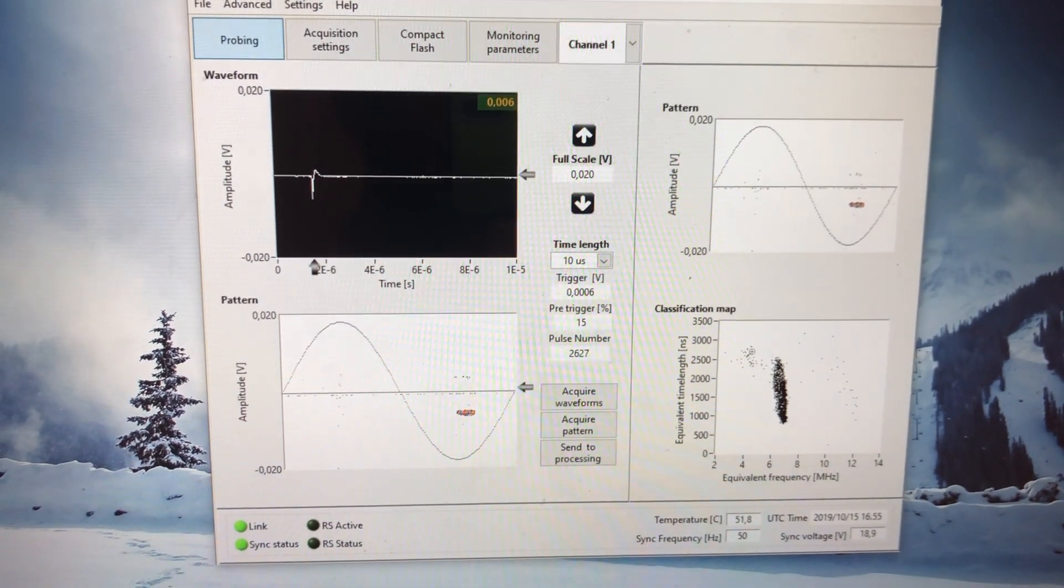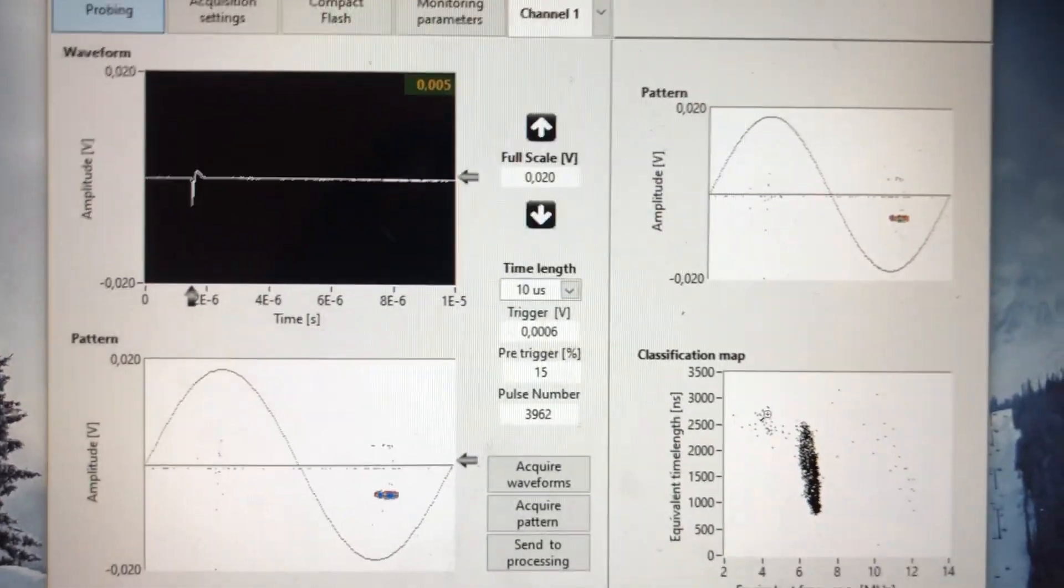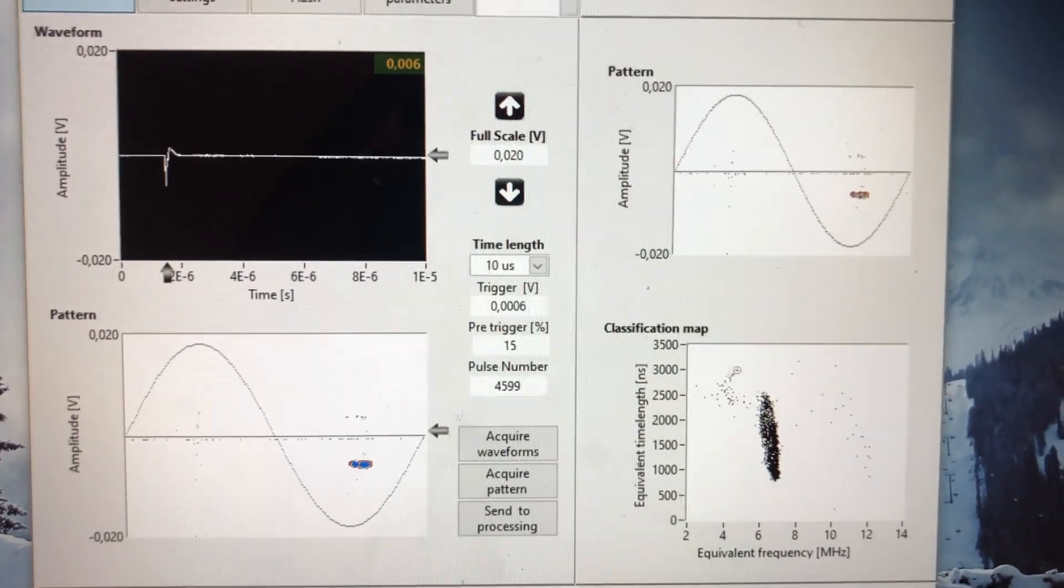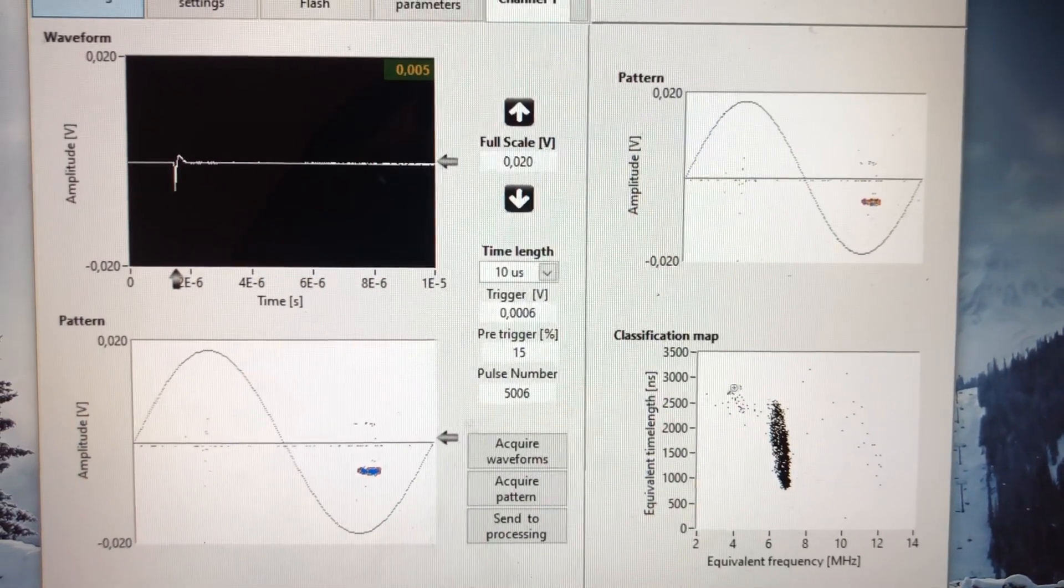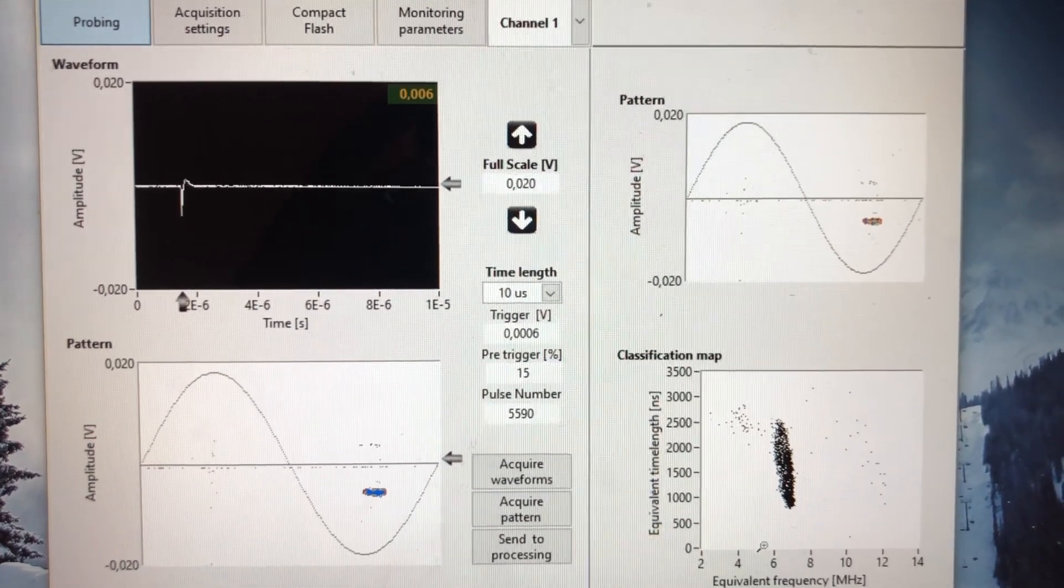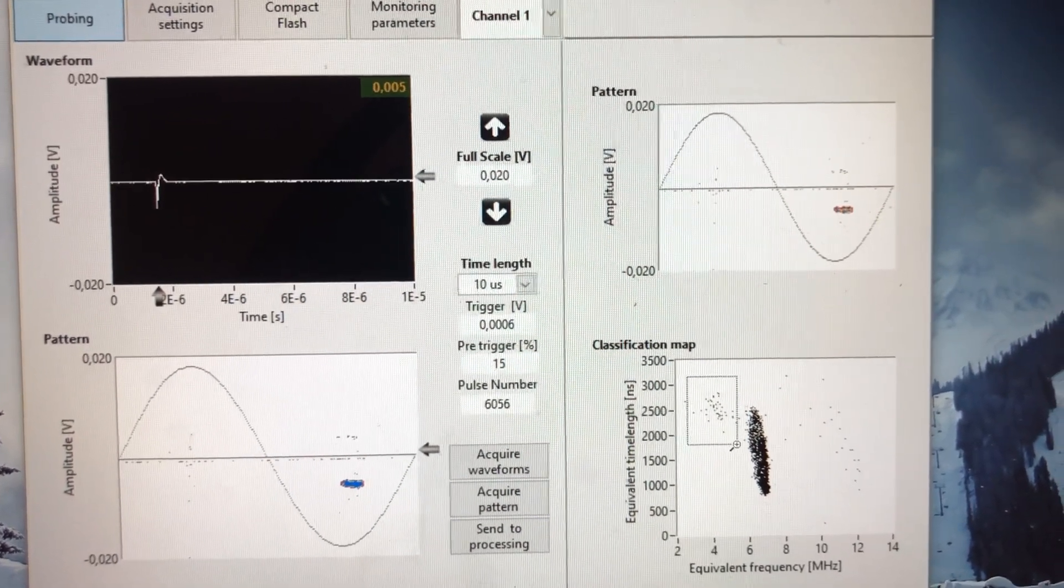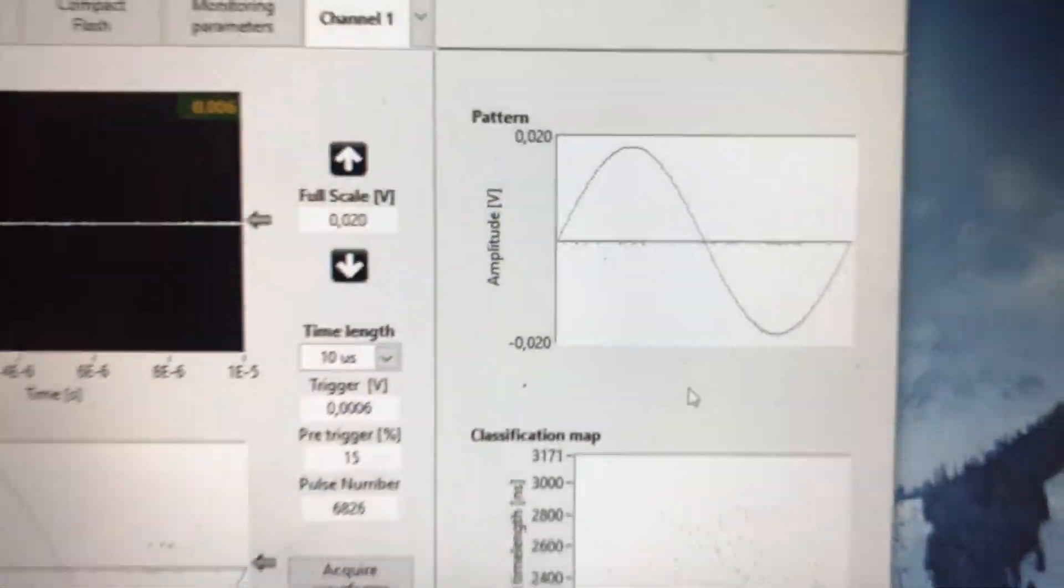Now, these two clusters actually represent two types of signals. They represent two types of signals. What I'm doing right now, I'm filtering this using what we call a TF map. This is a classification map. What I'm going to do now, I'm going to choose this cluster, and I'm going to see what it represents here. Then in the picture above, we see that this is now the noise which I saw before. It is not Corona.